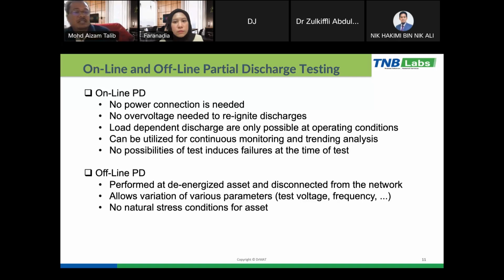And then for the offline PD, it means that we need to perform the measurement with the asset de-energized, or it means that we need to stop the operation of the equipment and disconnect the asset from the network. So through this offline PD measurement, it allows us to do more analysis. For example, we can test at different voltages, we can test at different frequencies. So we have more data to analyze in detail the condition of the assets. And also there is no natural stress condition for the assets. It means that we can test at a lower voltage, so we do not stress the assets.